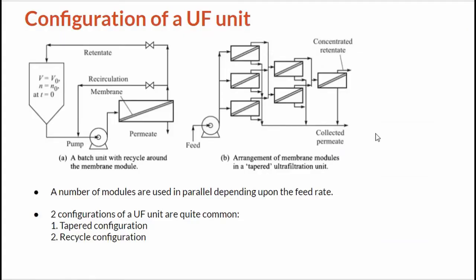Now we resume with the configuration of an ultrafiltration unit. In the figure, two configurations which are quite common are shown: the tapered configuration and the recycle configuration. In a recycle configuration, a part of the retentate stream is recycled back to the inlet of the module to achieve a higher concentration of the retentate. The strategy also increases cross flow velocity and thereby reduces membrane fouling. In the other configuration, the modules are arranged in parallel series pattern. Since the retentate volume decreases after the liquid passes through module, a lesser number of modules is provided in the successive stages.